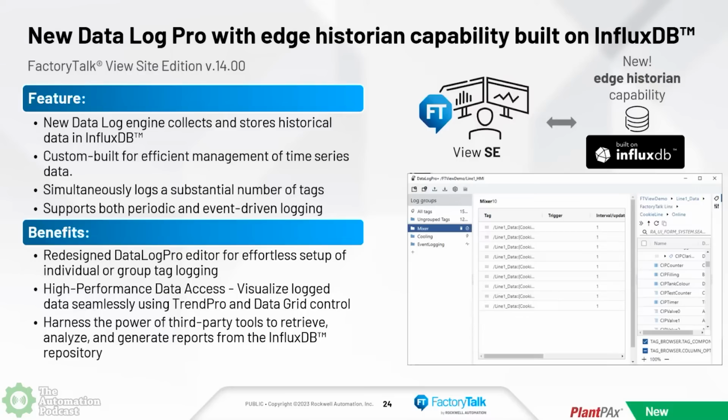Once you've done that, now you have the capability of saying, do you want to log this periodically? Do you want to do it event-driven? And there's another one that's on demand. And there are some properties associated with that you can filter in there, something like deadband. But the nice thing about this, as quick and easy as the configuration is, you'll save it, and it'll start logging the tags without you even having to issue a command to start. Oh, nice. So we do have commands to stop and start the services, but once you do it for the first time, you don't have to actually initiate it, it just starts logging.